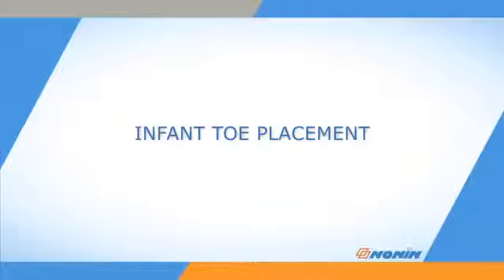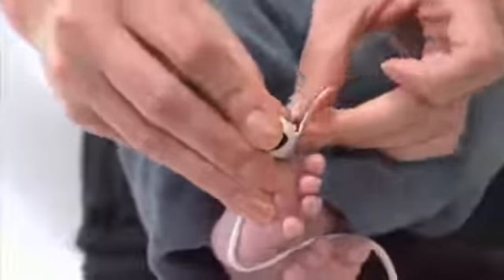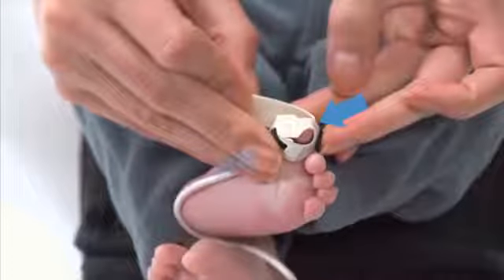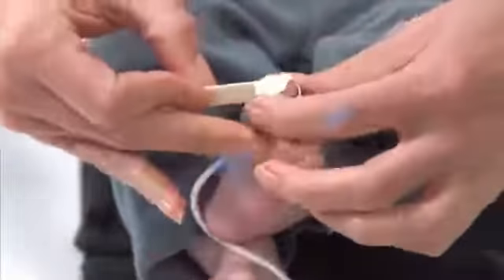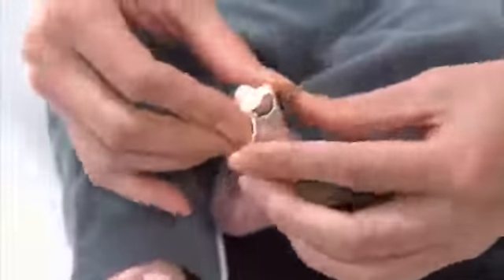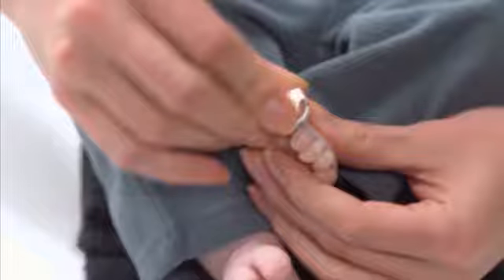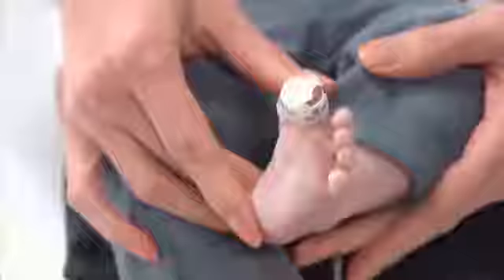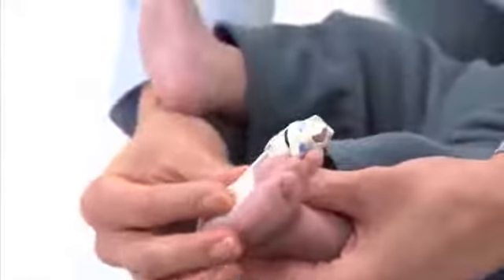For placement on the large toe of an infant over 4 pounds in weight, place the adhesive and detector portion on the bottom center of the toe, with the cable running back toward the heel. Now, wrap the sensor on top of the toe, placing the emitter on the top of the toe, across from the detector on the bottom of the toe. Gently wrap the tab over the tip of the toe to overlap and secure the sensor to the toe. It's a good idea to gently secure the sensor cable independently from the sensor along the bottom of the foot toward the heel.